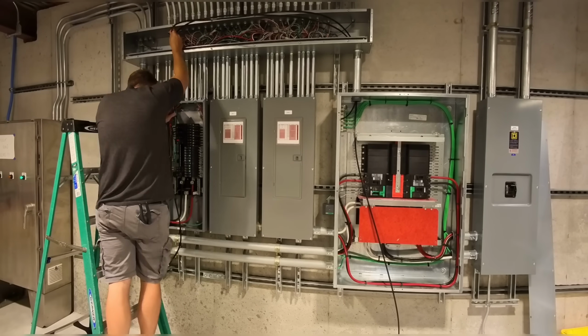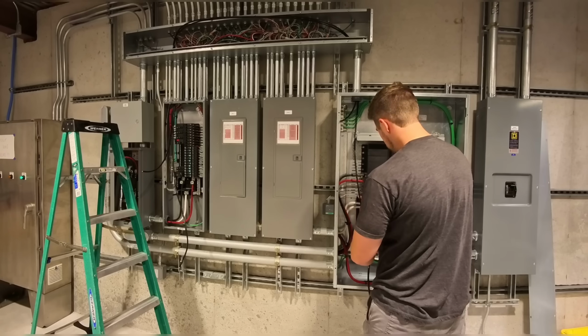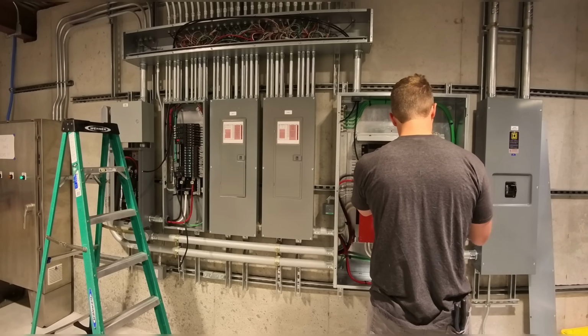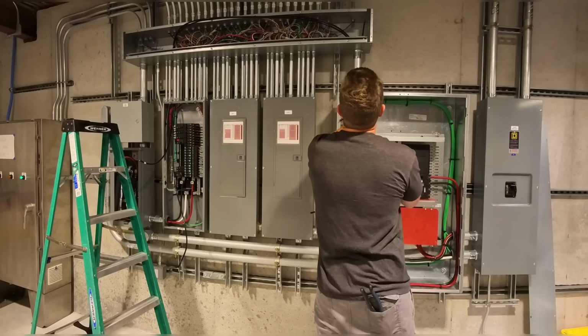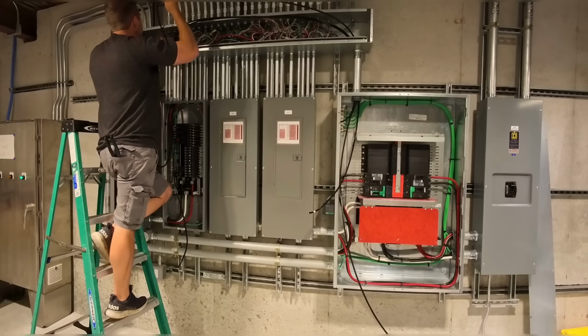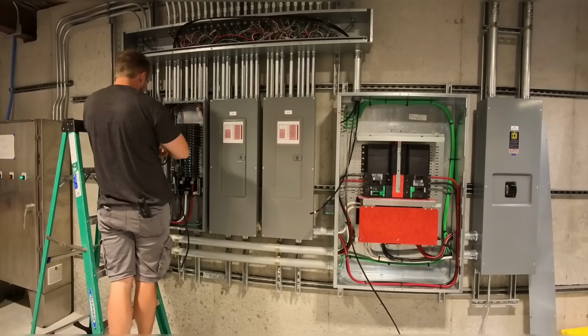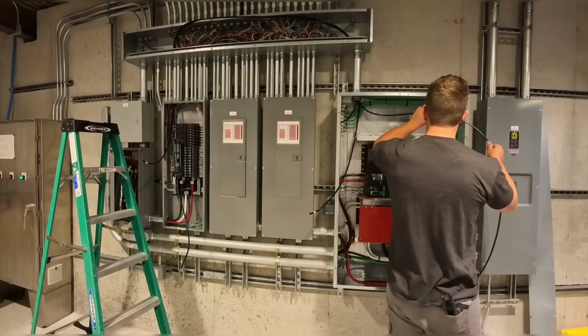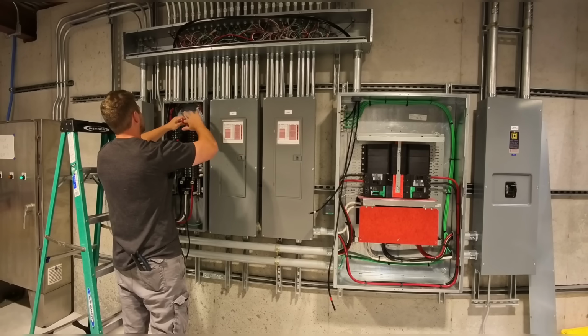Now, in theory, if that wire were to completely catch fire or turn red hot, it's all enclosed in the trough and the piping, so I'm really not worried about that. And the fault would have to occur between the two panels, because if the QO panel starts drawing too much, it is protected by a 100 amp breaker on 100 amp wire.